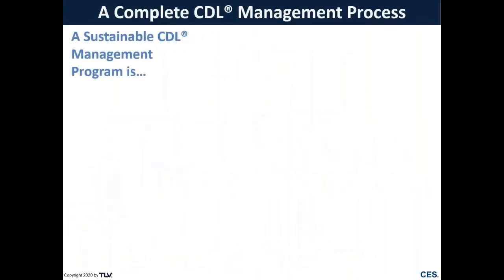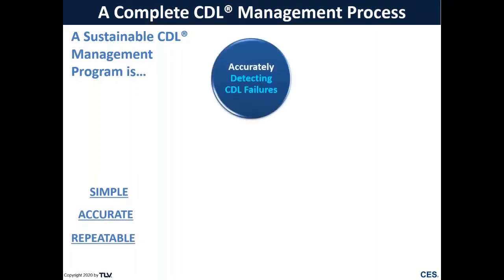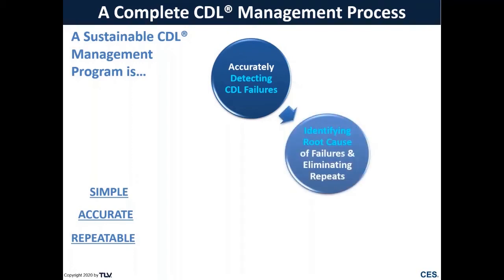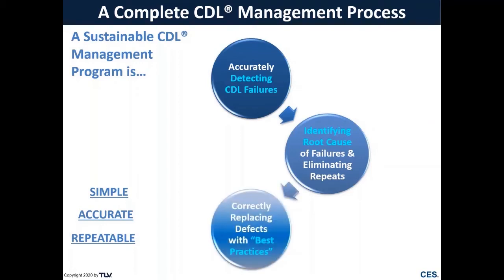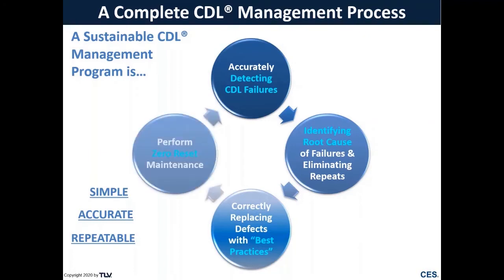What should a CDL management program look like? First, it needs to be simple, accurate, and most importantly, repeatable — a program, not just a one-time survey. It starts with accurately detecting CDL failures, not just steam trap failures, identifying the root cause and eliminating it. Ultimately, replacing defects with best practices — best practice steam traps or corrected piping — and performing what we call zero reset maintenance, or ZRM, resetting your failure state to zero so ideally 100% of your steam traps and CDLs are properly functioning.